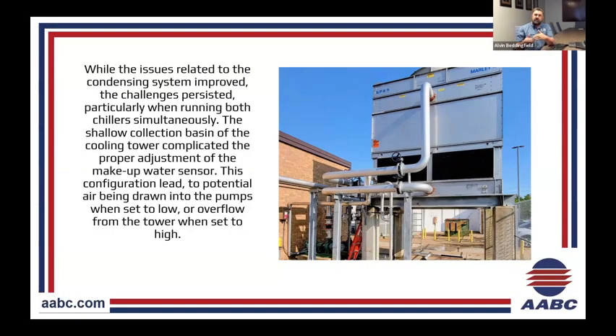And the complication was that the tower is spec'd to be able to handle it. Obviously, that basin's really, really shallow. So either the mechanical contractor and even the tower manufacturer had a very difficult time trying to teeter-totter where that overflow had to be set. We'd either go too low and start pulling air back into the system, and then, okay, we're back at square one, or we raise it up, and then we dump even more water into the street.